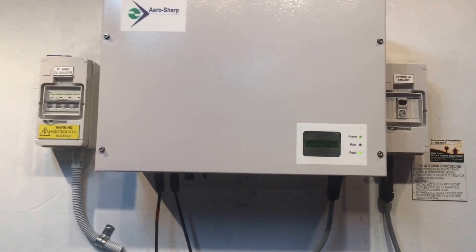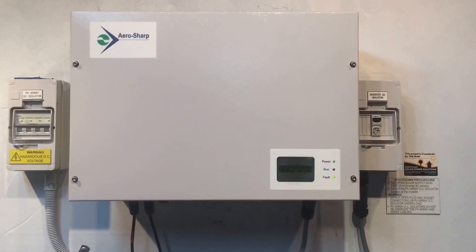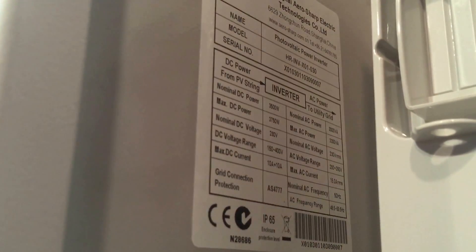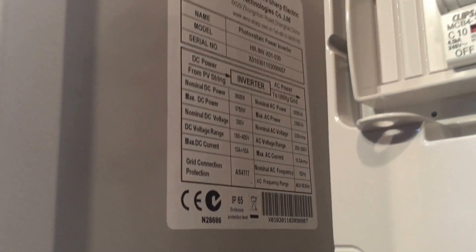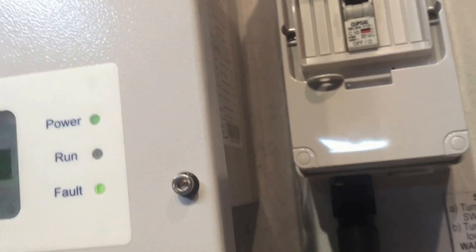Whatever you do, it's always important to know the size of the inverter, which you can find on the data plate on the side of the inverter. The model is HR-INV-X01-030 — that '030' at the end means it's a three kilowatt inverter. Over here where it says nominal AC power, it says 3000 VA, which means three thousand watts — three kilowatts.